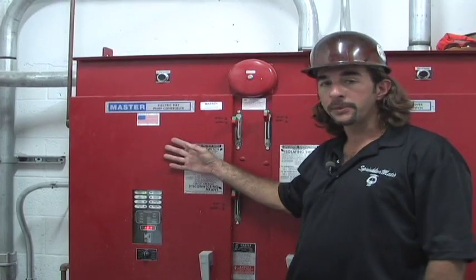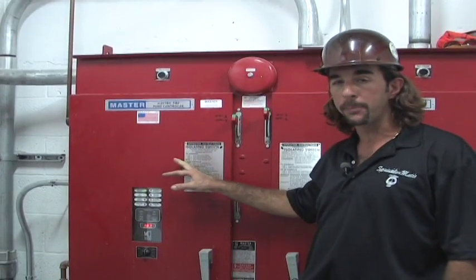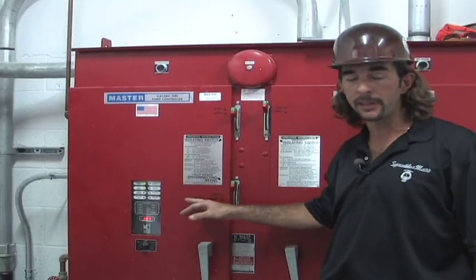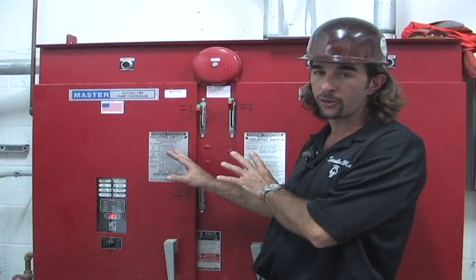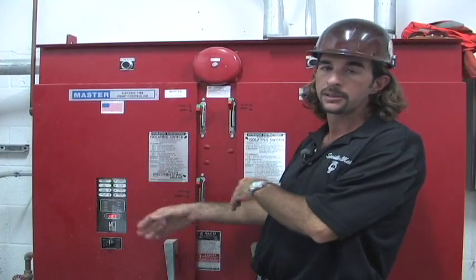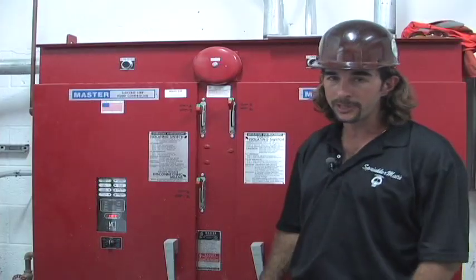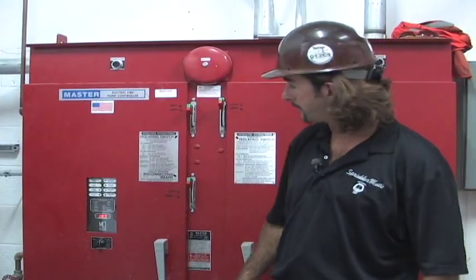This is our fire pump controller. We're going to run through the basic operation of the weekly test that should be performed by maintenance. For video purposes, we're going to strictly work on looking at the controller right here with the fire pump running. Then we'll turn around and repeat ourselves with the fire pump going over here. It's going to get a little noisy in here, so I'll try to speak up so we can understand me when the fire pump's running.